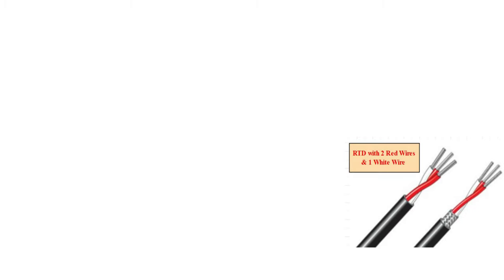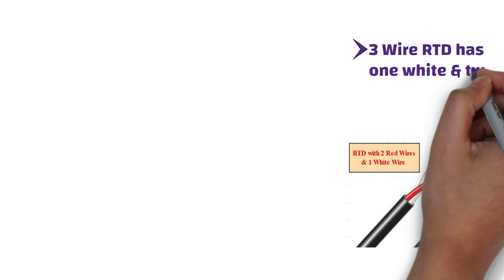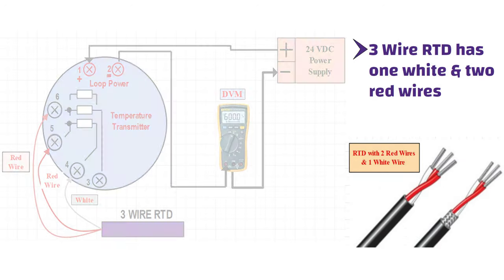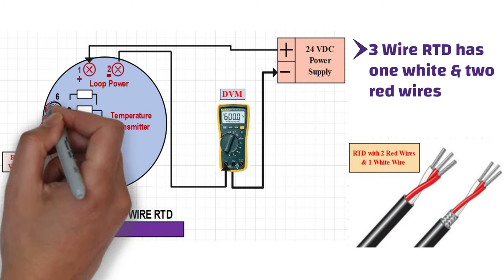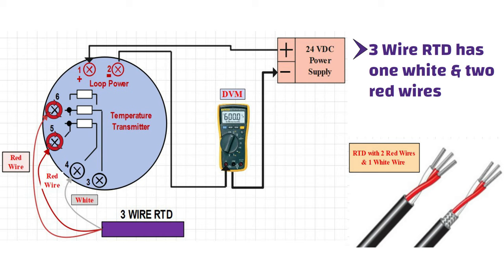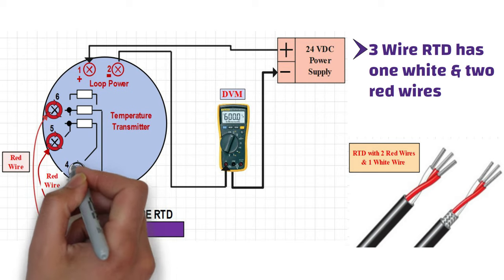As you can see from the picture, all 3-wire RTDs have one white and two red wires. So one red wire will be connected to terminal number 5, another red wire will be connected to terminal number 6, and the white wire will be connected to terminal number 4.